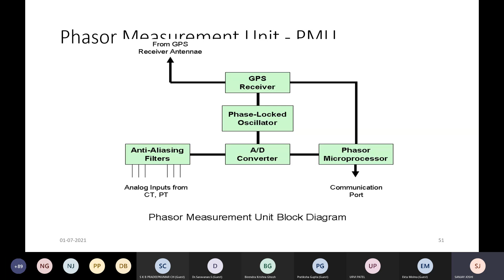It is required to be filtered for anti-aliasing, since some other frequency components can be present if we use this kind of technology. Then the analog signal is converted to digital, and the phasor microprocessor calculates the phasor, which goes to a communication port for transmitting it to the energy management system.